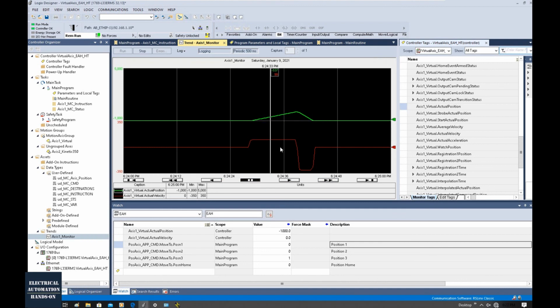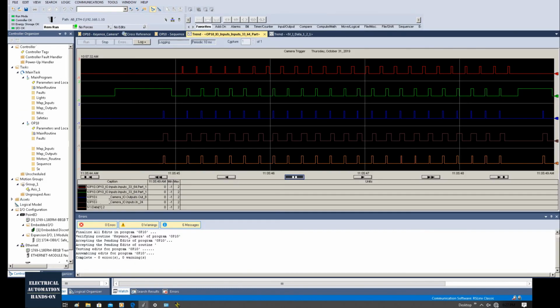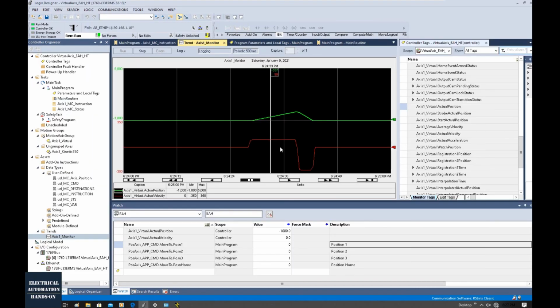So next time you can double click this trend file and you can open that again and monitor the online variables. All right, that is the trend or curve tools built into this RSLogix 5000 or Studio 5000 software. That is a very commonly used tool, or convenient tool, when we're doing on-site commissioning or test or doing some analysis. Other than the motion command test, we can still use this tool to test our logic or some other variables. All right, that is for today.